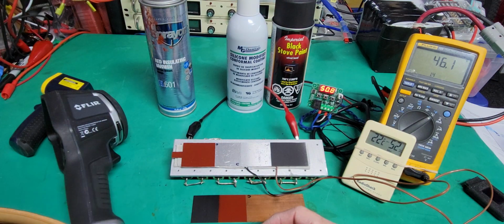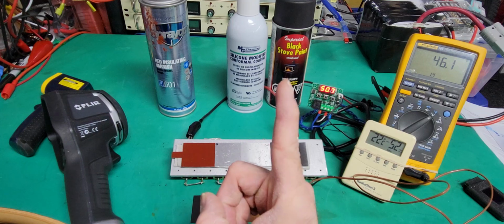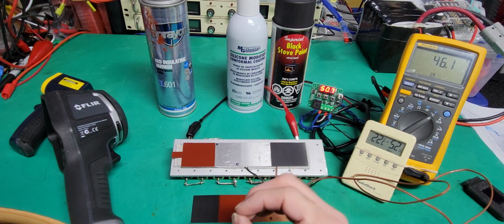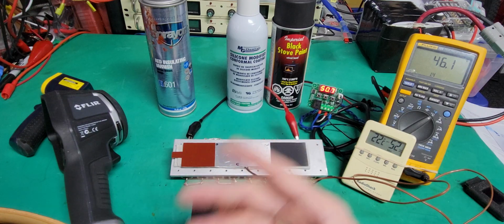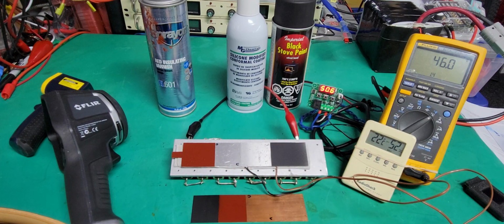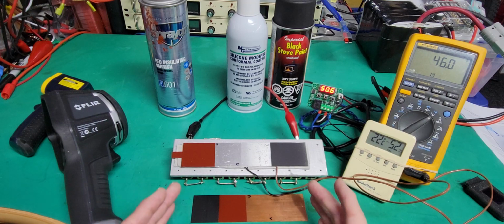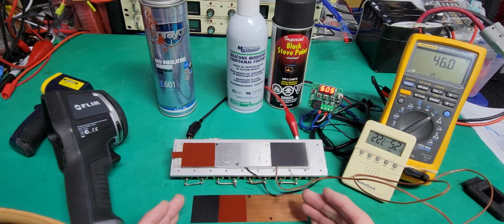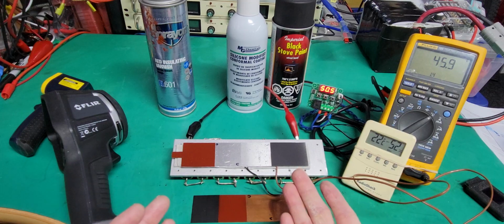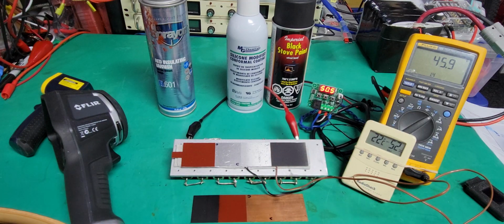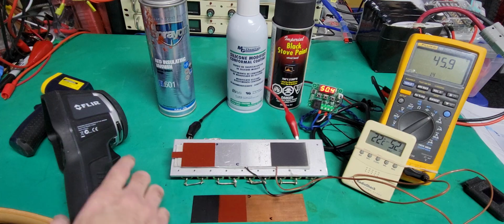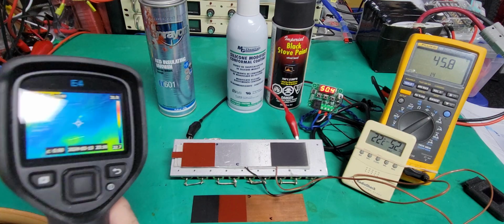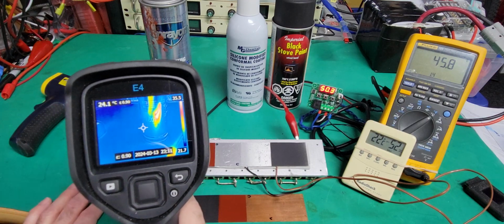Emissivity is normally a number between 0 and 1. It cannot be 1.2 or 4 or 10. It's between 0 and 1, 1 being like 100% and 0 being 0%. When a surface has a high emissivity, it will emit heat by radiation very easily. When the emissivity is low, it's the opposite: it will not emit or receive heat easily. Okay, so I will show you why the thermal camera sees things differently, and you will find it very interesting.